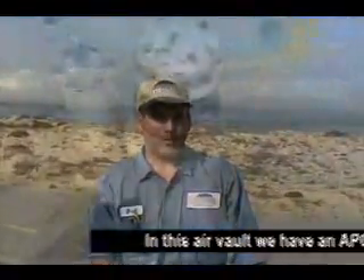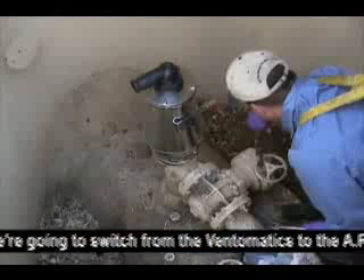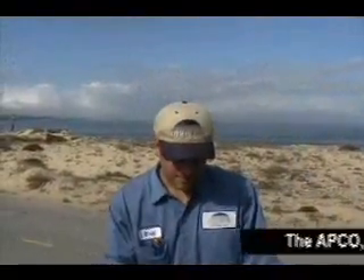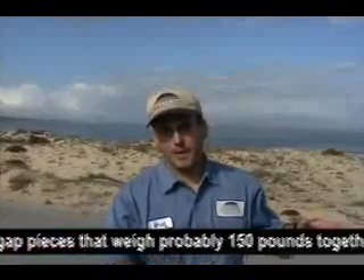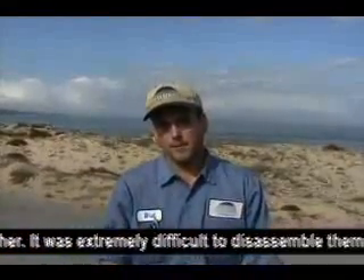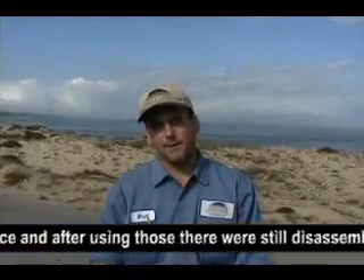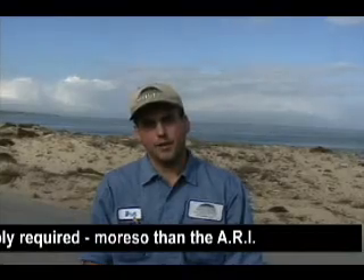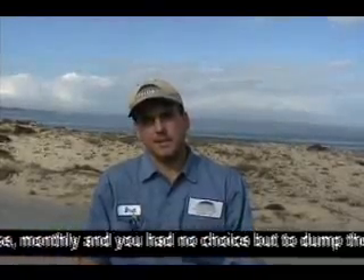In this air vault, we have an APCO, and we switched to a Ventomatic on half of it to try it out. Now we're going to switch from the Ventomatics to the ARIs on both sides. The reason we switched from the APCOs — it's a combination unit with two actual air gap pieces, and they weigh probably 150 pounds together; it was extremely difficult to disassemble them. The Ventomatics were the newer device, but after using those, there was still more disassembly required than on the ARI. The APCOs were supposed to be serviced monthly at stations with a lot of grease, and you had no choice but to dump the grease.